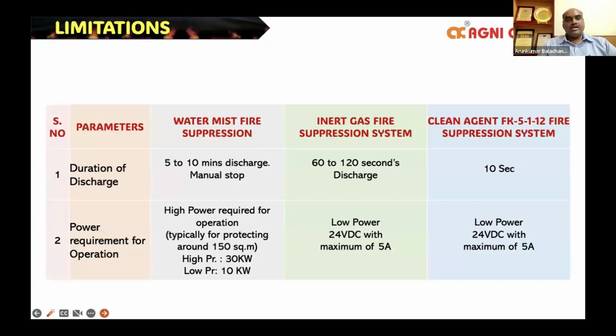So we'll just see a comparison of the limitations. I'm going to discuss only four parameters. First, duration of discharge. For a water mist system, it is approximately 5 to 10 minutes of discharge. And the stop is always manual in a water suppression system, being a pump, so we can stop whenever the fire is suppressed or extinguished. For an inert gas suppression system, the discharge varies between 60 to 120 seconds. And for a clean agent or a chemical agent, it is within 10 seconds.